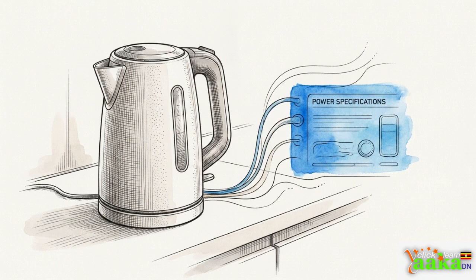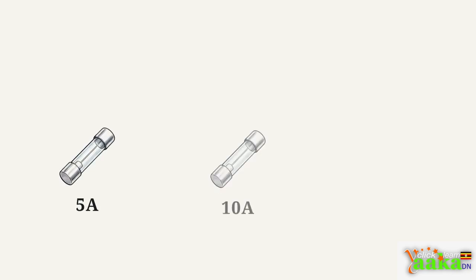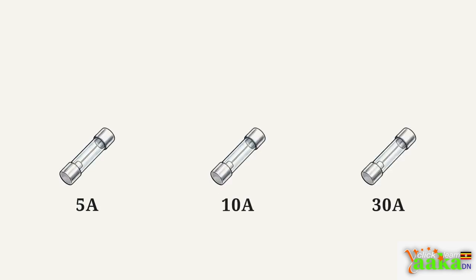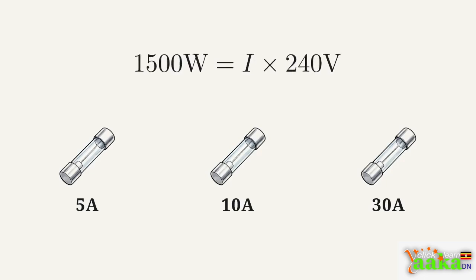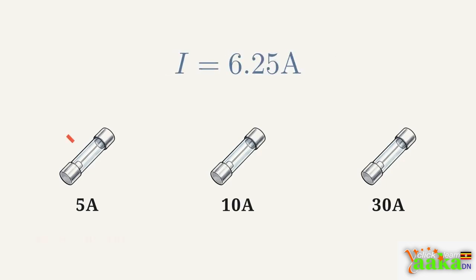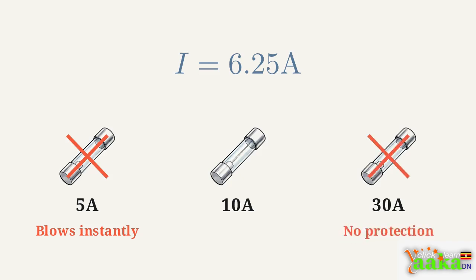For a final challenge, consider an appliance rated at 240 volts and 1,500 watts. To keep it safe, would you use a 5 amp, 10 amp, or 30 amp fuse? Using P equals IV, we find the normal operating current is 6.25 amps. A 5 amp fuse would blow instantly. A 30 amp fuse is far too large. It wouldn't break the circuit during a fire. The correct choice is 10 amps, the next standard size.